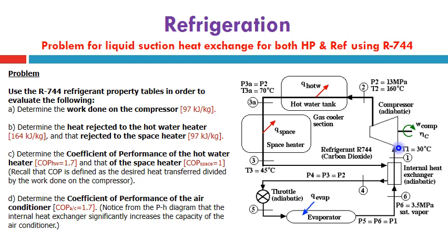line of the compressor to reduce the temperature of point 3 from 45 by a certain degree of subcooling or without subcooling, by decreasing its temperature by gas cooling, not subcooling, since there is no condensation process, as will be shown on the next slide when presenting this line diagram on the P-h diagram dedicated for CO2.